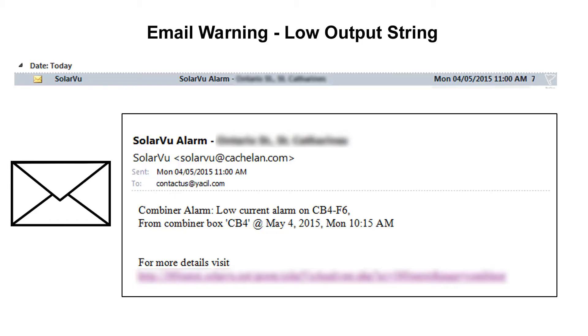A few hours after the system started generating today, SolarVu sent this email alarm warning that a string was producing below the alarm threshold entered in setup. Click on the link in the email to go directly to the combiner screen in the analyzer tools so we can see what the problem is.